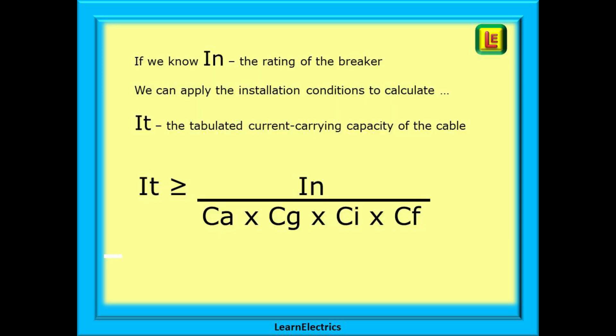Once we know IN, the rating of the fuse or breaker, we can apply the installation conditions to calculate IT, the tabulated current carrying capacity of the cable. Tabulated means that we look up this value in a table, and find a cable size that will take this value of current. The formula in the on-site guide is shown here, and includes the 4 most often used condition codes. The formulas shown in the Wiring Regulations book are basically the same, just lots more C factors.